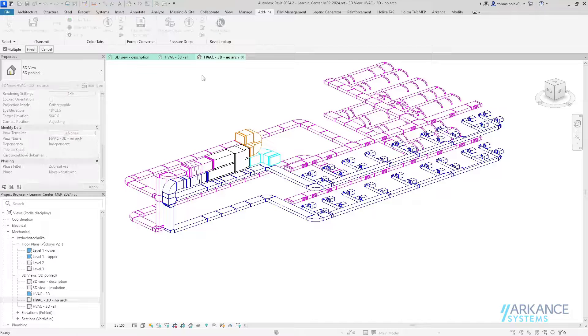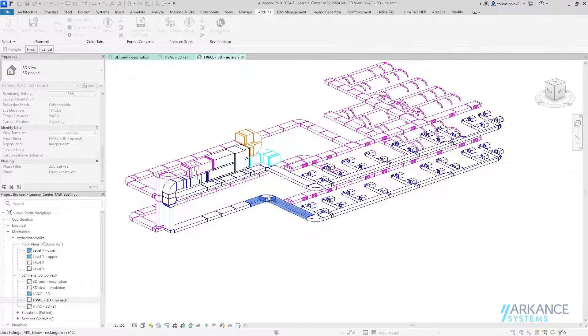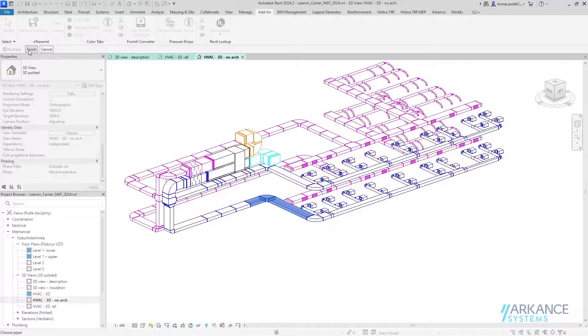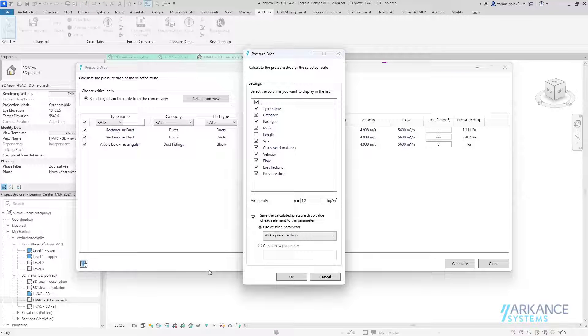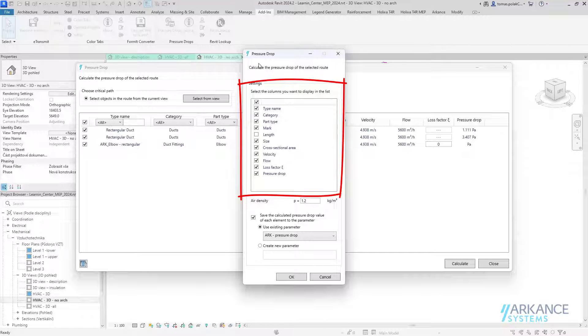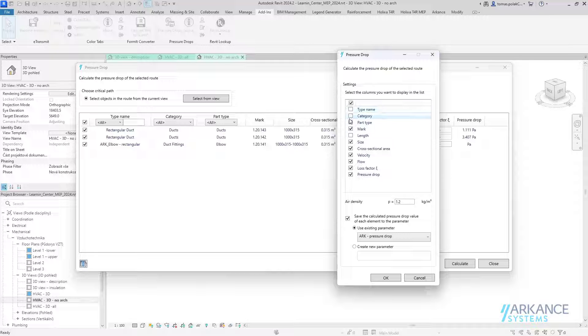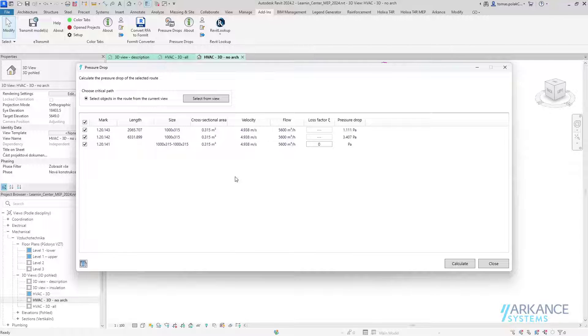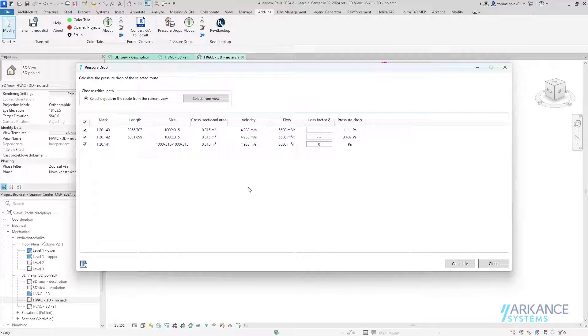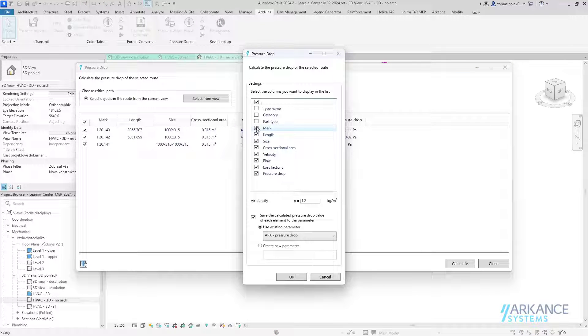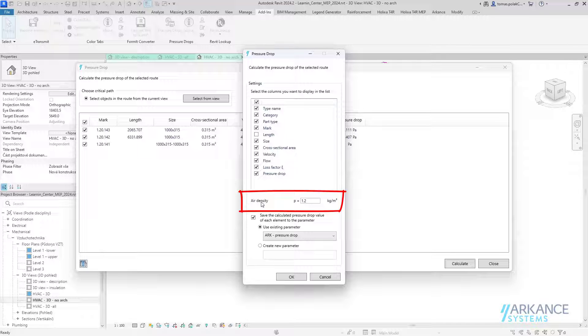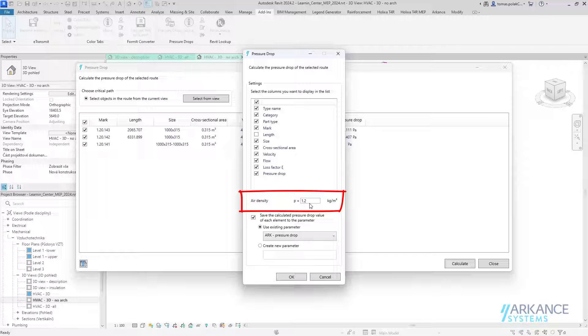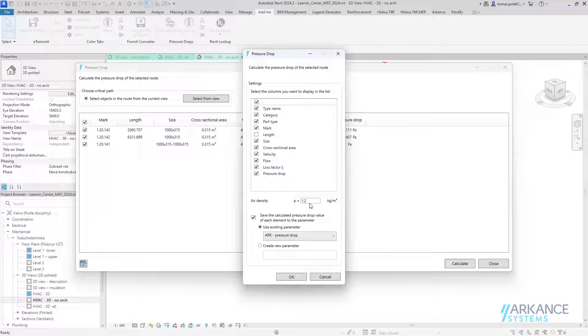Now let's take a look at some other options in the settings. I can start the tool first and then select the elements for calculation. Here in the settings, I've got options for which columns I want to see. If I don't care about the type name, category, and part, and I want to see length, I hit okay and I see only the columns which I selected. What is also set here in the settings is the air density, which is used for the calculation. In my area, we use the standard air density of 1.2 kg per cubic meter. This is all the settings of the pressure drop plugin.